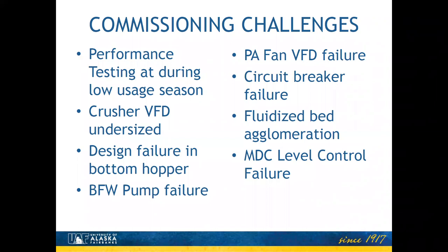And then in the course of doing that, we encountered a failure with the generator circuit breaker. It wouldn't close, and an electrical generator isn't very much good to you if you can't connect it to anything and let the power flow somewhere. So the vendor on that was quite responsive, and it turned out to be a fairly minor item to fix, but we got past that.